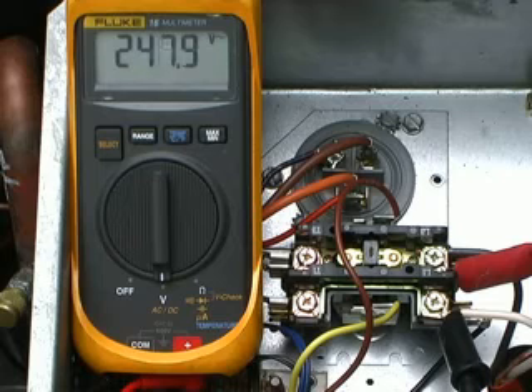But back to number one, if you open up the panel and you see the contactor is actually pulled in, then you hook your probes to the inlet side, and as you see, we're reading 247 volts, so we know it's coming in. So the next thing to do is go to the other side of the contactor and see if you're getting 240 out.